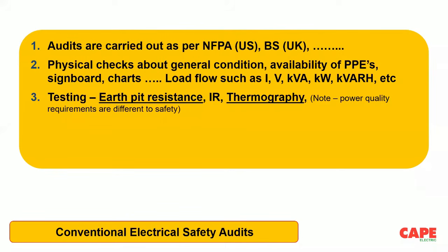In almost all electrical safety audits, testings are carried out. I have put 3 testings which are generally carried out. Not all 3 are generally carried out. The first one, earth pit resistance, the resistance measurement of the earth electrode, is always carried out. The second one, IR, insulation resistance, is not done very carefully, but sometimes the IR measurements are done. And thermography. In modern buildings, thermography is done because people believe that by making a thermography, you can achieve safety, which is absolutely not 100% correct.